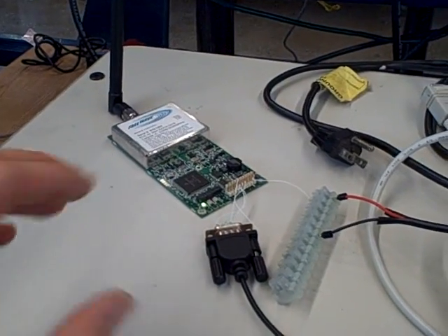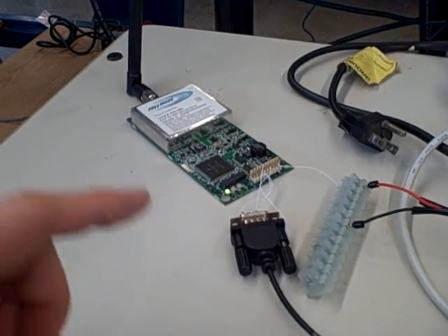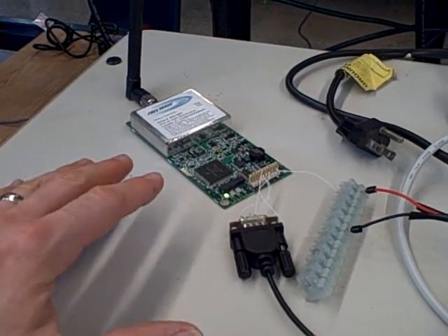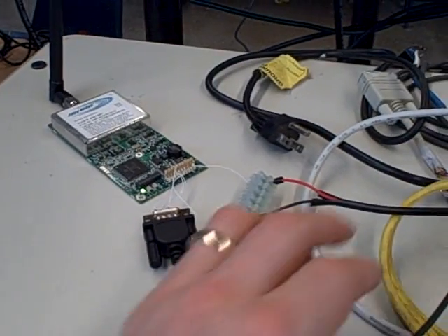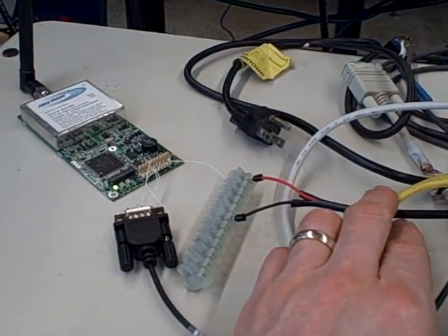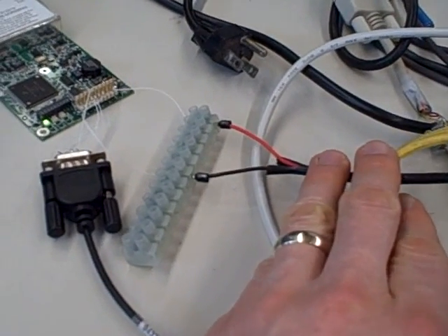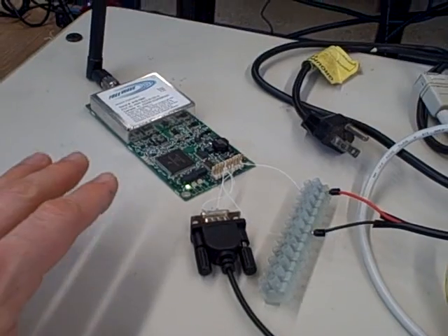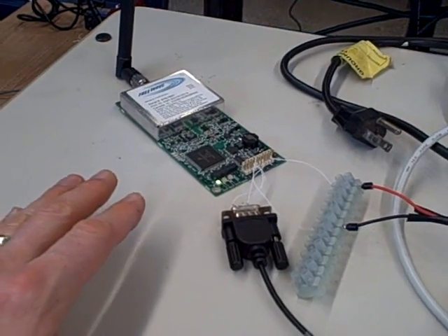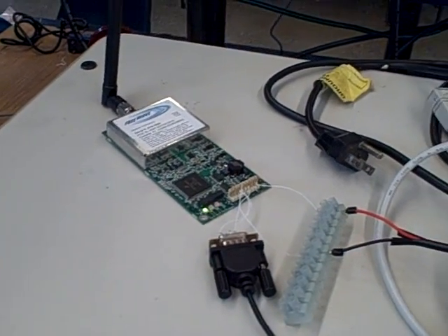And as a result, when it would transmit, the battery voltage would dip down and this would begin to have errors. So we connected a nice AC DC 24 volt power supply. That's a much more stable power supply for the radio units and now they are working just flawlessly.